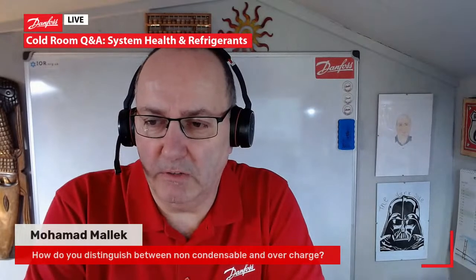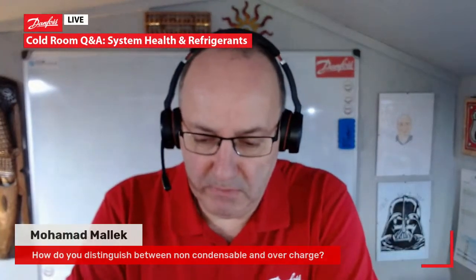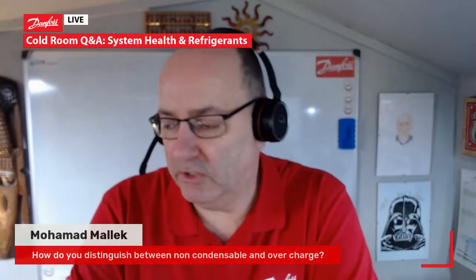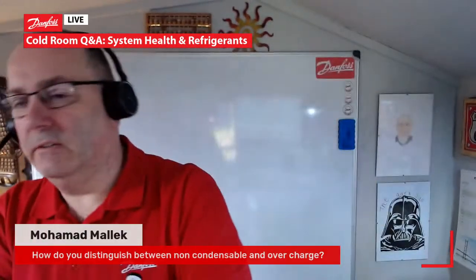So Mohammed asks a question: how do you distinguish between non-condensable and overcharged? Well, if you've got non-condensables in your system, just turn the system off, let the pressures equalize out, and your pressure in your system should be equal to our lovely comparator. If it's not, then you've got non-condensables in there because your pressure is higher. So always use your pressure temperature relationship on your comparator or on your phone, and that will tell you whether you've got any non-condensables in your system.